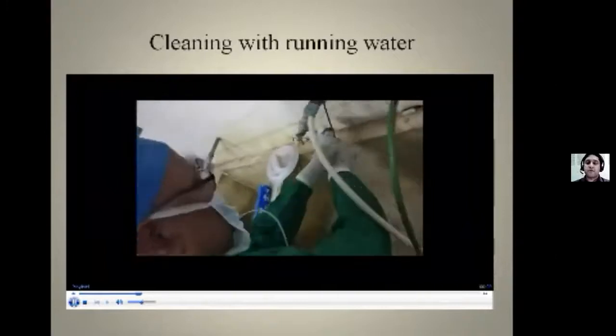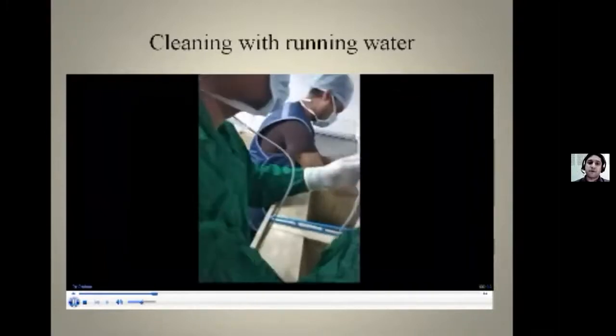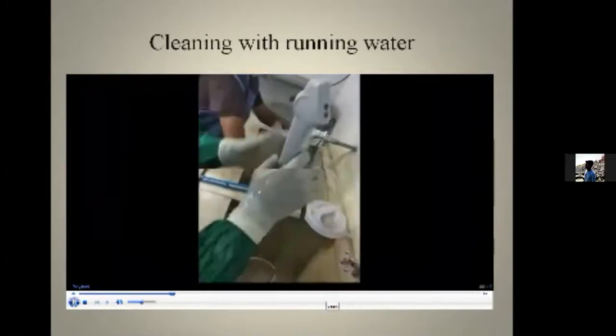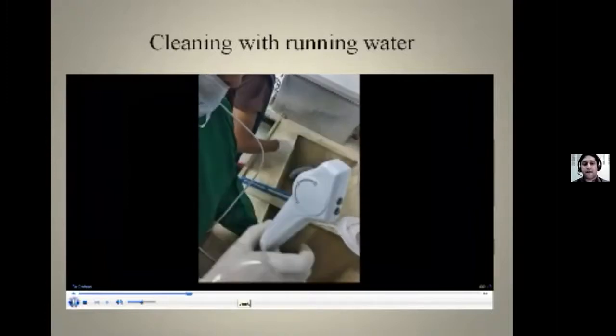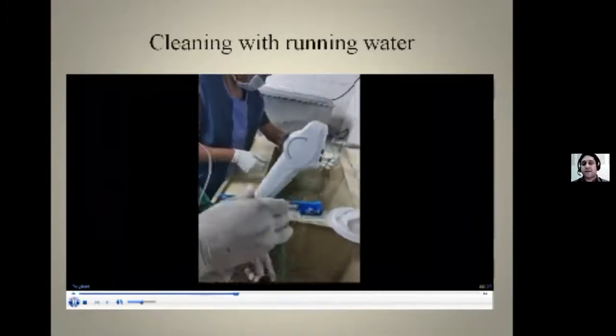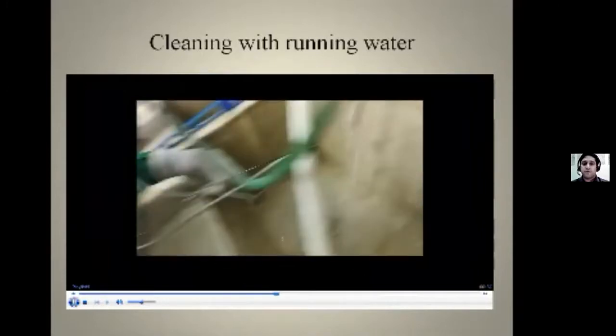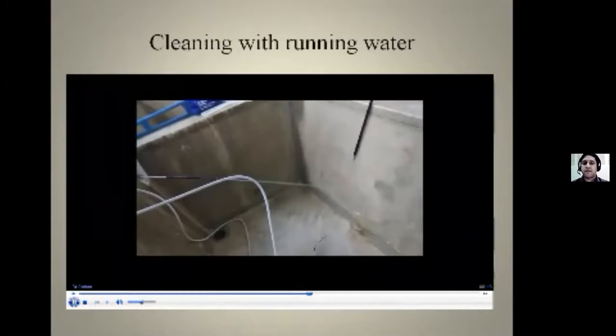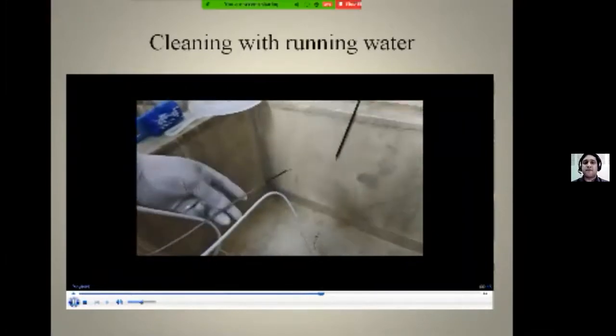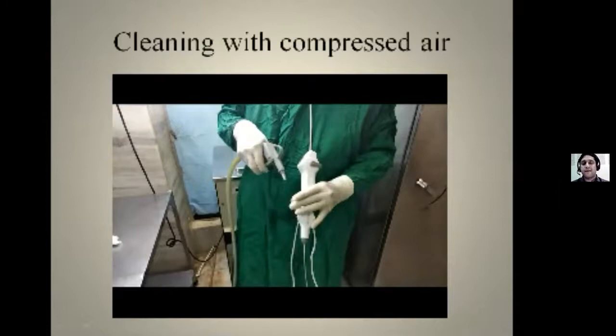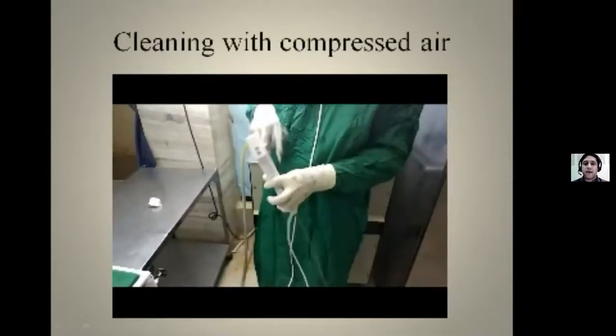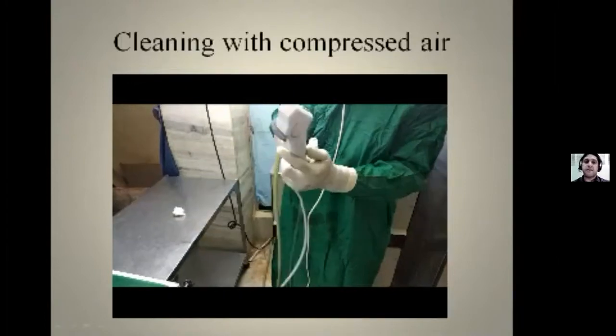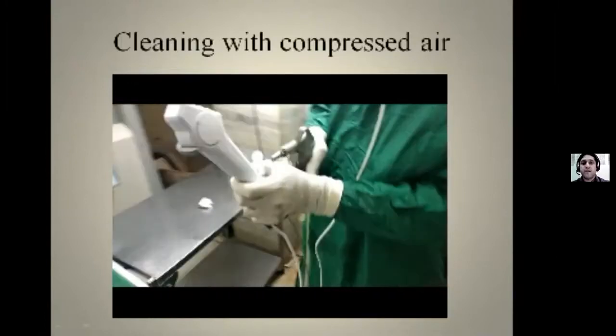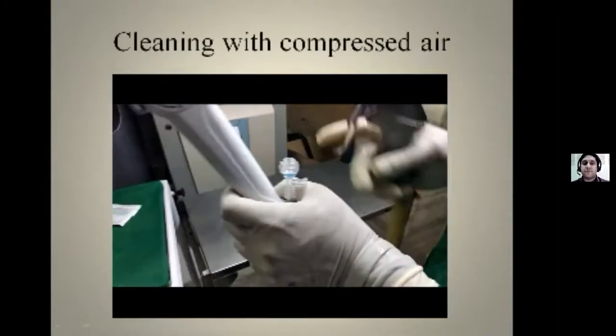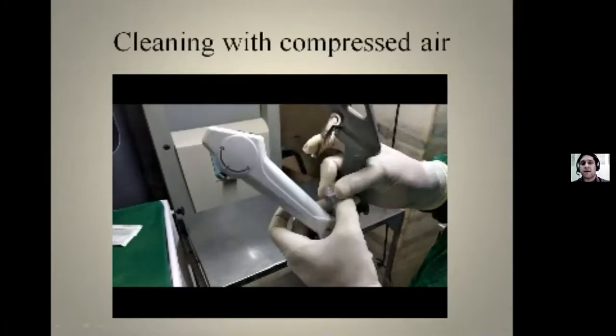There is some hypochlorite solution added in the water also, that is 5% hypochlorite solution. With the help of a water jet system, we clean the water jet of the flexible ureteroscope. Here we see the water jet entering the lumen of the ureteroscope. So all the debris is cleaned off with the running water. After that comes cleaning with compressed air. The compressed air dries up the scope and the lumen is also cleaned with it. Here we see all the lumens and channels being cleaned with compressed air, that is, the channels have also been dried.